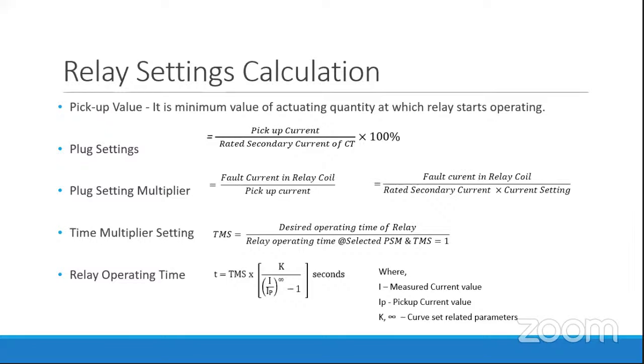Before going to the calculation, there are certain terminologies which are used for relay settings. That is the pickup value. It is the minimum value of the actuating quantity at which the relay starts to operate. It means the minimum value at which the relay should trigger and give the tripping command to the circuit breaker.